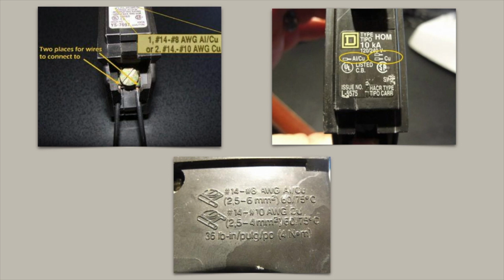Double tapped wiring is okay if the circuit breaker is designed for 2 conductors. If a circuit breaker is designed for 2 conductors, this will be identified on the right side of the breaker, and the terminal of the circuit breaker will be constructed to hold 2 conductors in position.